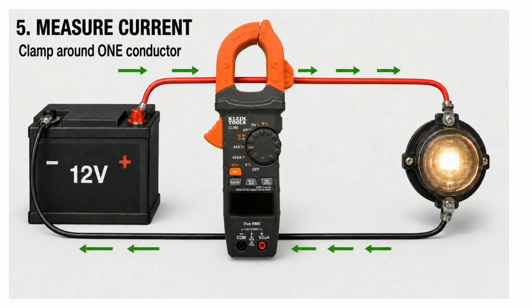If both the red and black wires are inside the clamp, their magnetic fields normally cancel each other. The meter may show close to zero even though current is flowing. The same rule applies to an AC power cord. The clamp must go around only one current-carrying conductor, not around the entire cord. The number on the display tells us how many amps are flowing through that one wire.